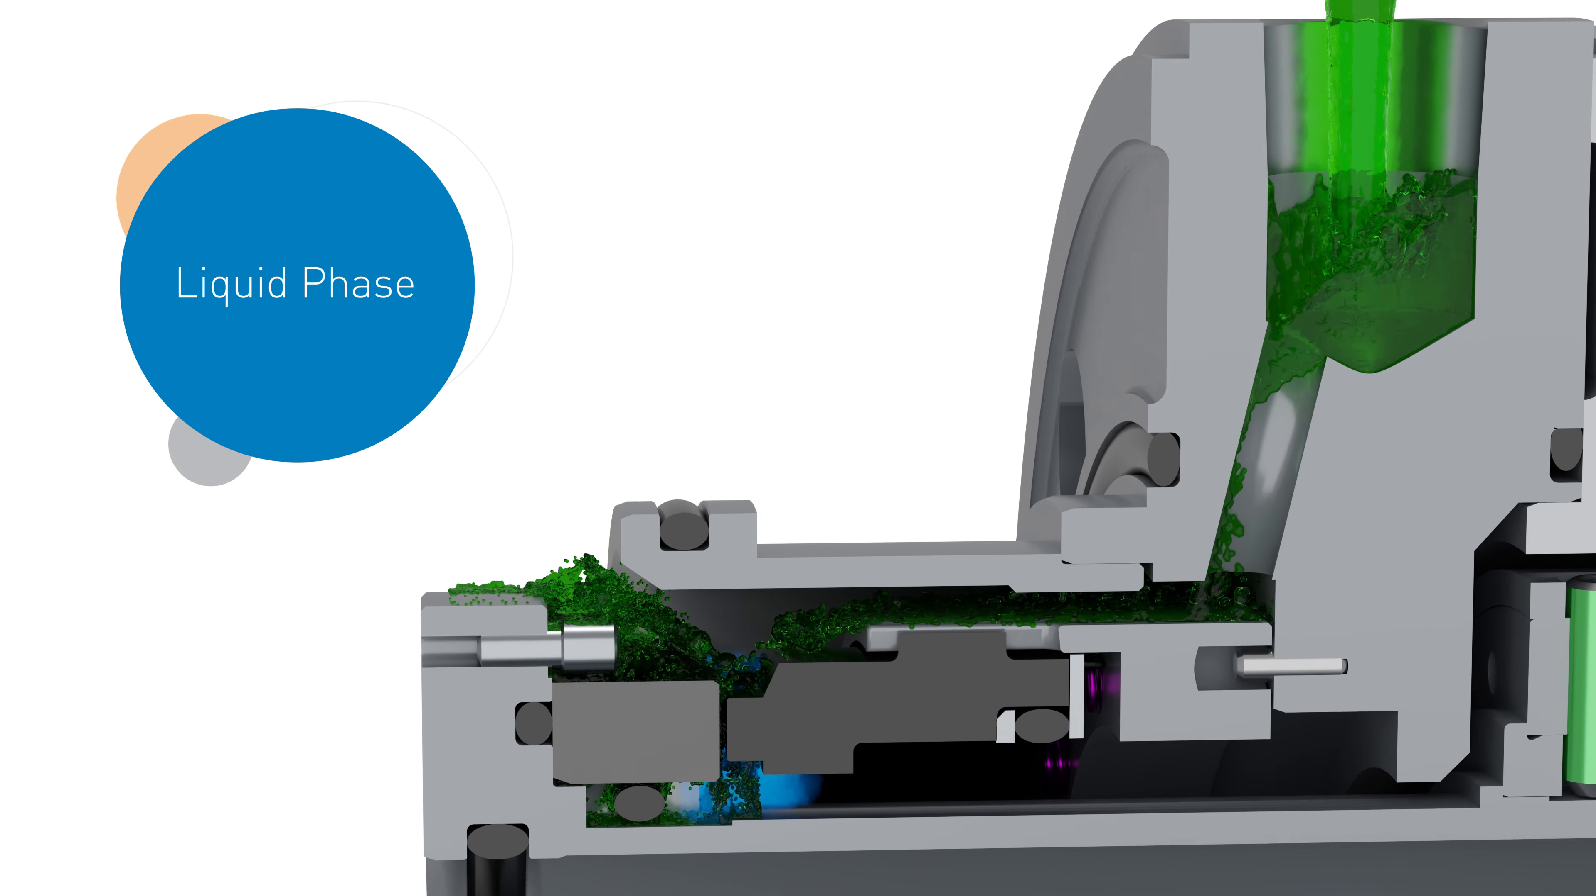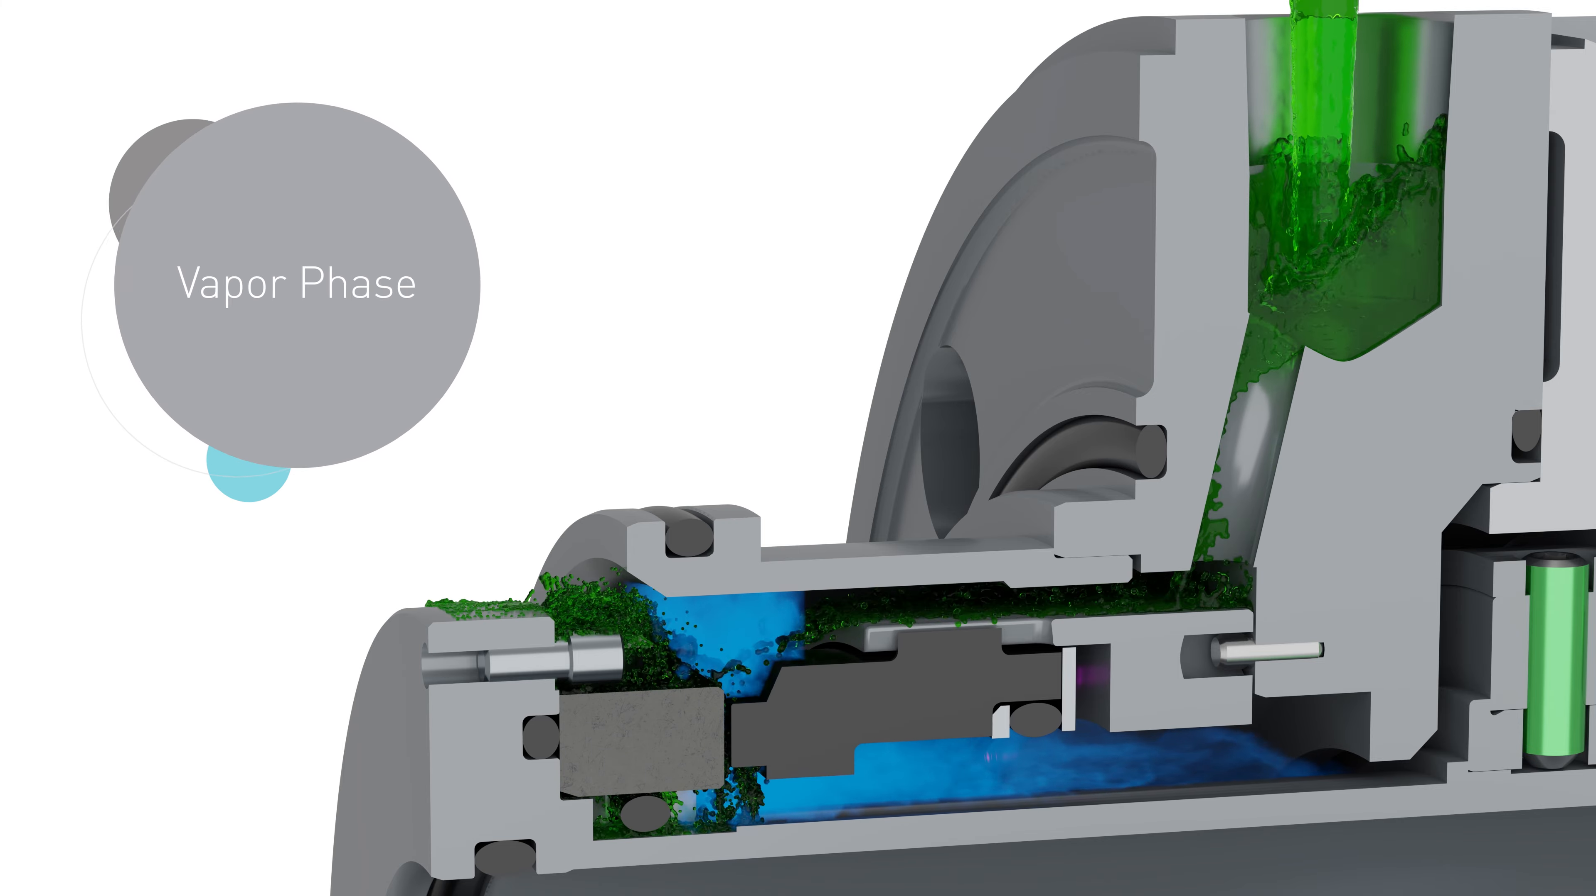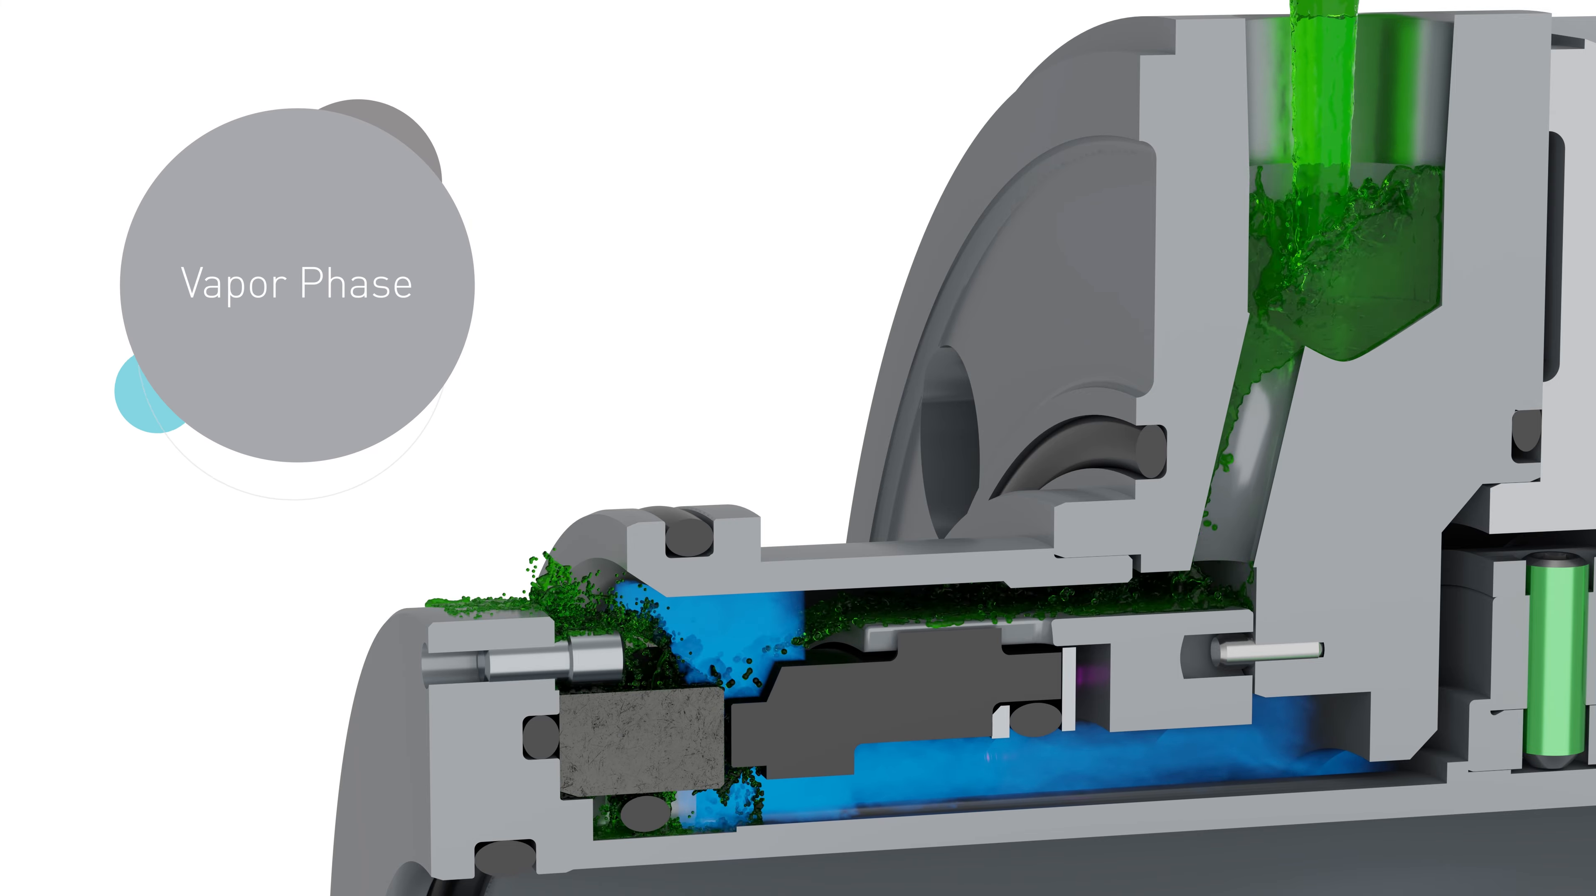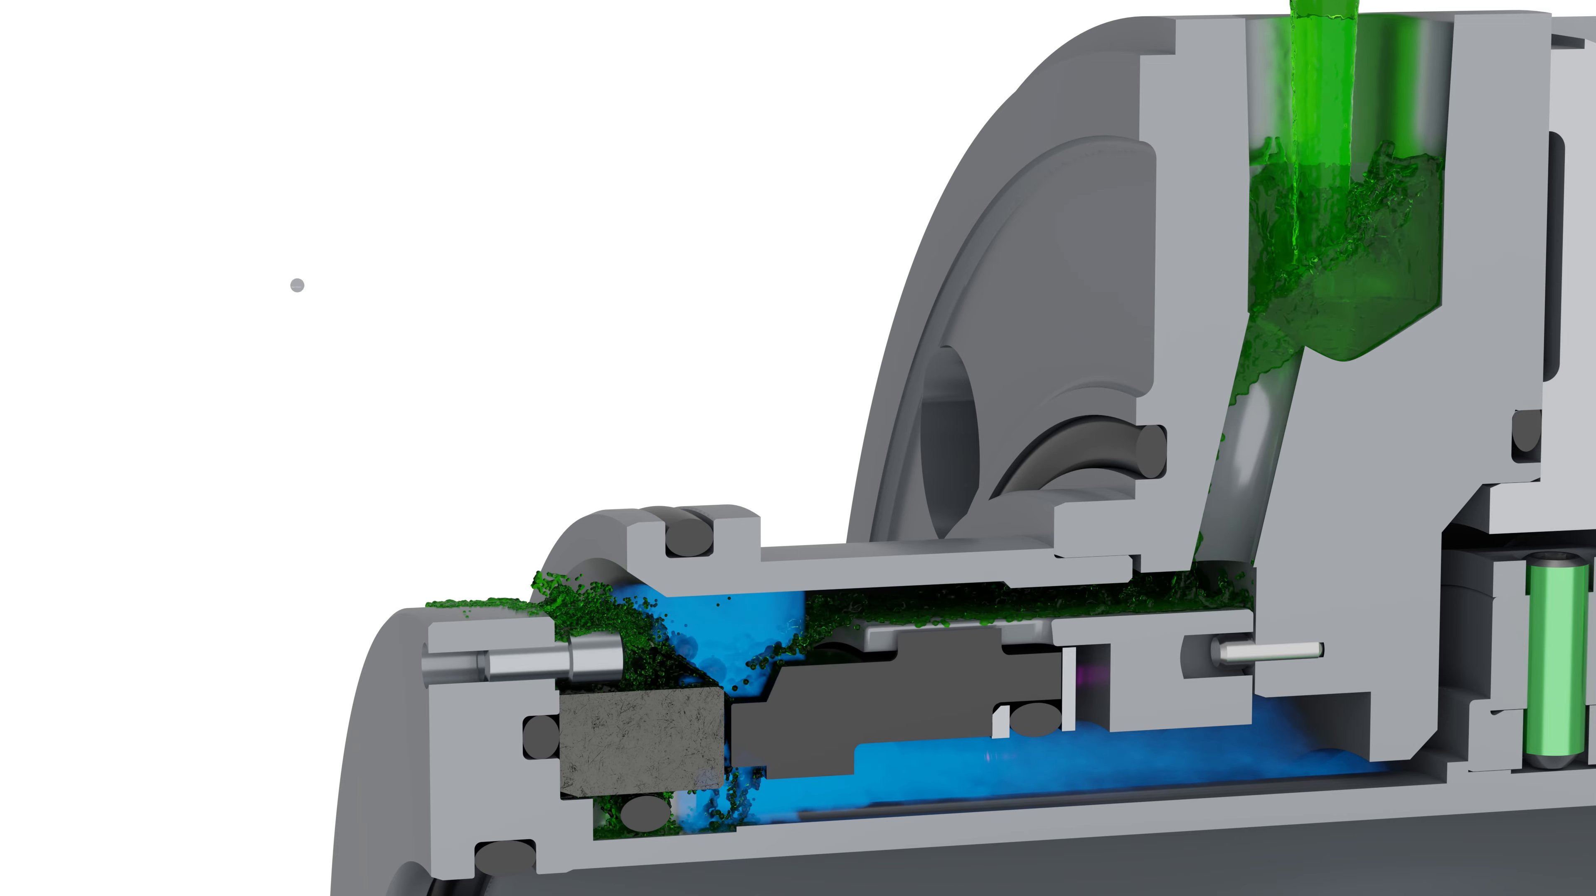As lubrication is diminished, more heat is produced, which increases the phase change to vapor. Ultimately, the result is premature face wear and reduced seal life.